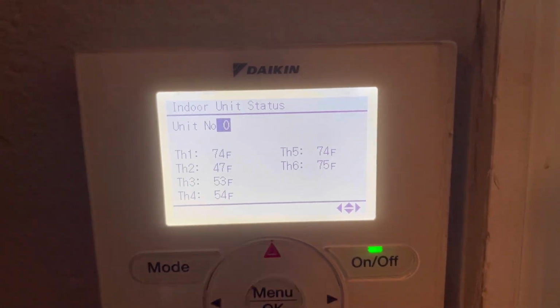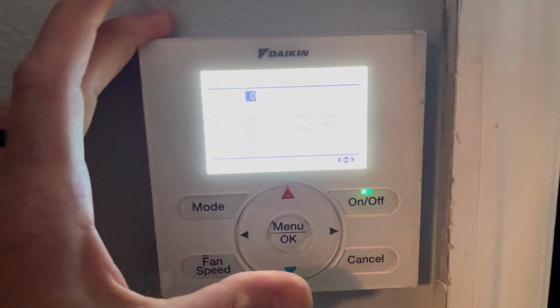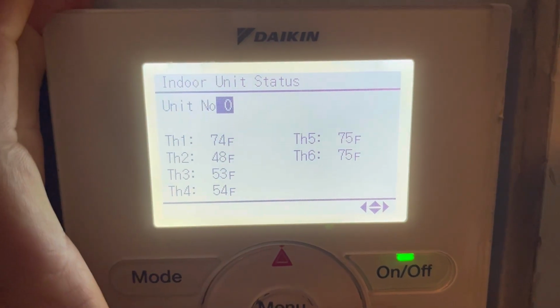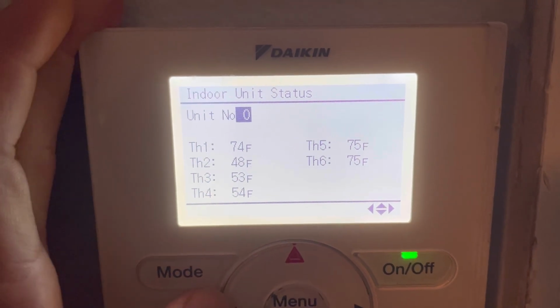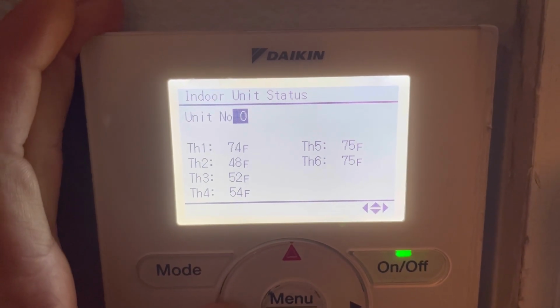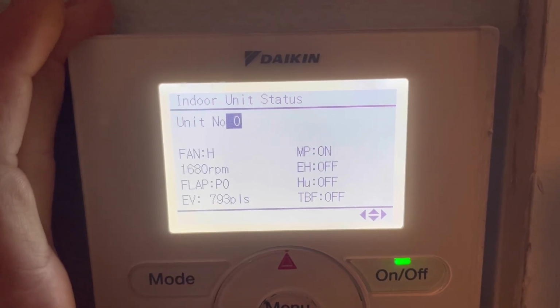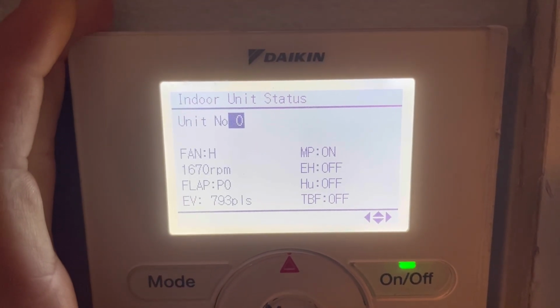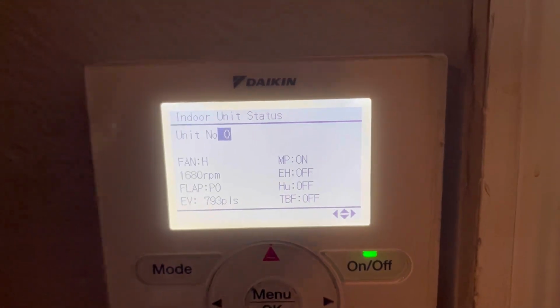And if you don't have one in the room, I always recommend that you at least have one of these on your trucks at all time so that you can toss it on a system if you have to do exactly this. And now you can see here 48 and 53. That valve is probably going to start to close down because now I've overshot my 9-degree superheat and it's going to get lower and lower and lower. But yes, this is how you use the BRC controller for service aspects.